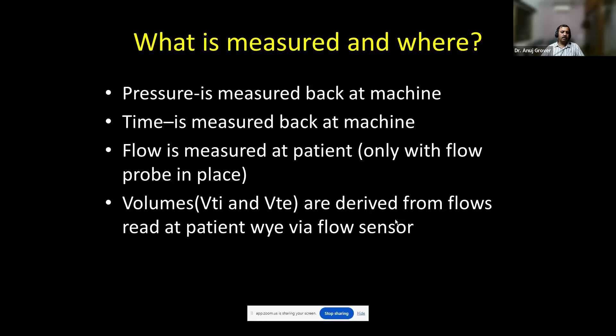So we all have seen flow sensors in our workplaces. So when you connect the ventilator to the flow sensor and the flow is going through that, there are 2 platinum wires inside the flow sensors. Now those are heated to 400 degrees. There is a constant current needed to keep them at that degree of temperature.